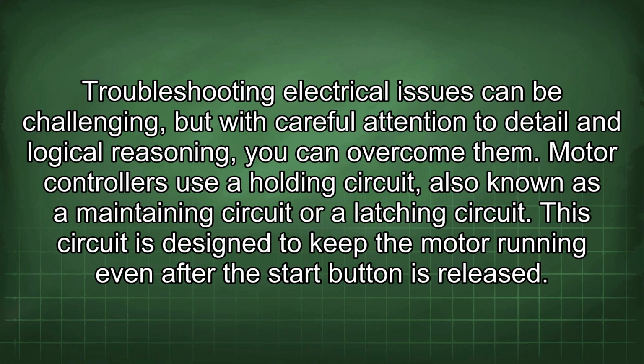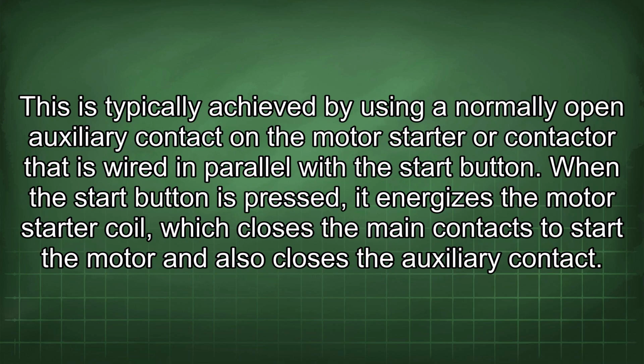Motor controllers use a holding circuit, also known as a maintaining circuit or a latching circuit. This circuit is designed to keep the motor running even after the start button is released. This is typically achieved by using a normally open auxiliary contact on the motor starter or contactor that is wired in parallel with the start button. When the start button is pressed, it energizes the motor starter coil, which closes the main contacts to start the motor and also closes the auxiliary contact.